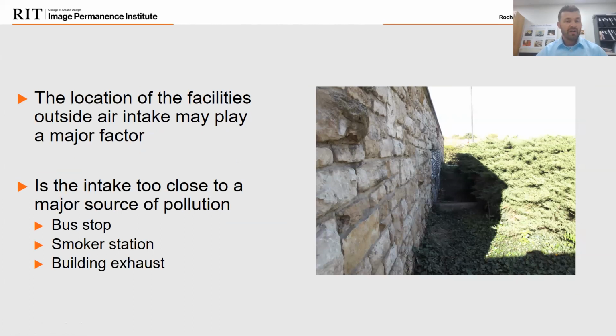The image that you're looking at here on the right is an outside air intake from a facility that Kelly and I worked with. It's very hard to see. I'll turn my pen back on to really point it out, but the outside air intake is here. The reason it's hard to see is there was a tree growing out of it. So it's one of those things, what could happen? What could bring in some possible source of pollution? Aside from this little tree growing out of it, the bus stop for the facility was right outside of this window. It was just outside here. So that could play a major factor. What are we bringing in from that bus stop?